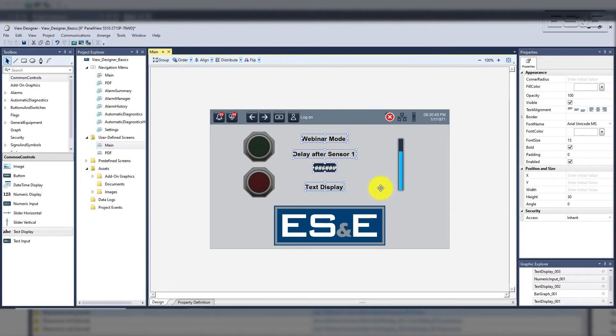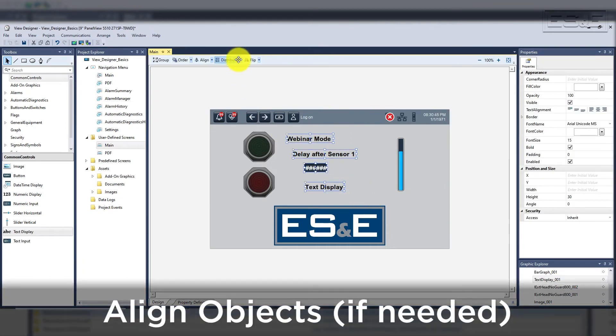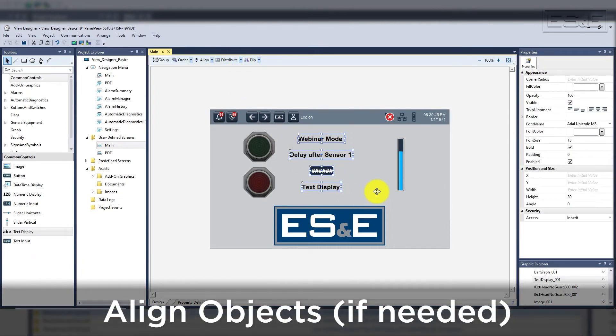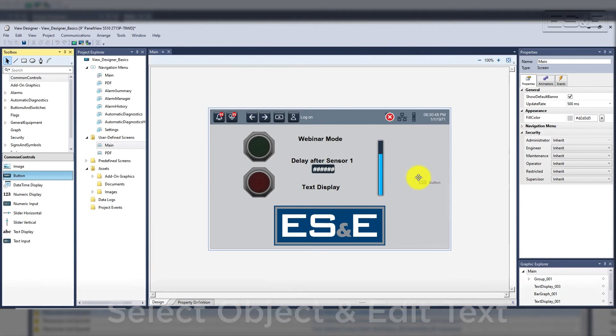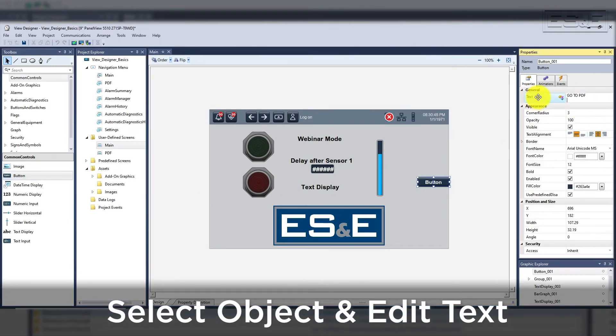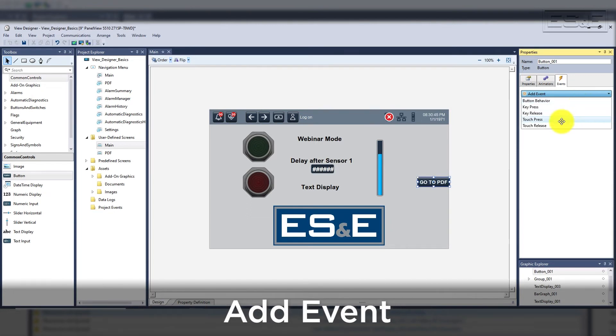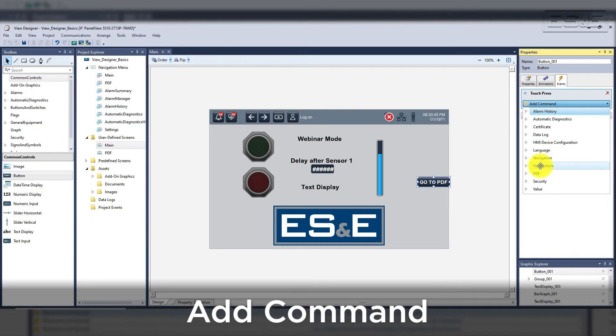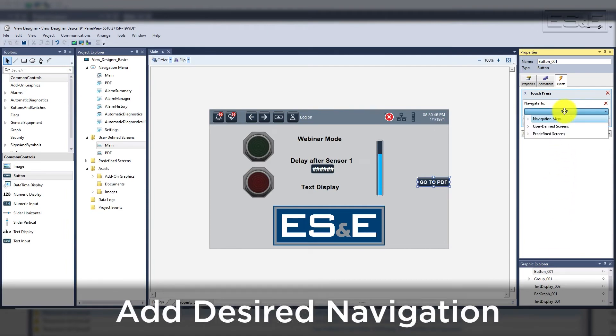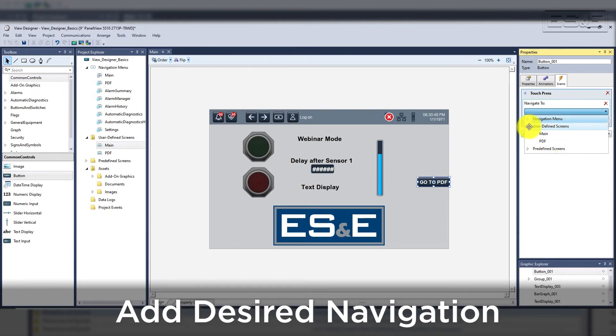Next we want to create some simple navigation between screens, but we should align our objects and group them to make alignment easier. This is not a necessary step but it is always good practice when creating screens. The next object will be a generic push button which can be turned into a navigation button. To start, we will change the text to 'go to pdf.' Now we will add an event to this button on the event tab by selecting touch press, then add the command by selecting the drop-down, picking navigation, then screen navigate. From there you get a menu to pick from the navigation menu, user screens, or predefined screens. We will select the user pdf screen. This could have also been accomplished using a button behavior, which shows the versatility of the buttons inside View Designer.